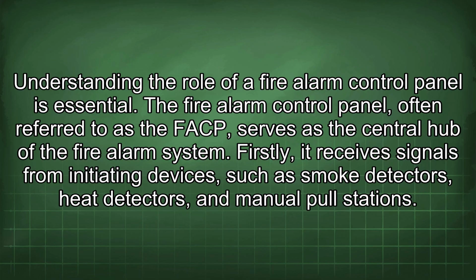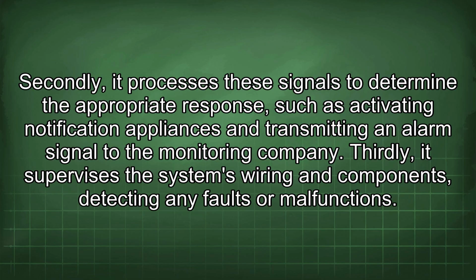Understanding the role of a fire alarm control panel is essential. The fire alarm control panel, often referred to as the FACP, serves as the central hub of the fire alarm system. Firstly, it receives signals from initiating devices such as smoke detectors, heat detectors, and manual pull stations. Secondly, it processes these signals to determine the appropriate response, such as activating notification appliances and transmitting an alarm signal to the monitoring company.